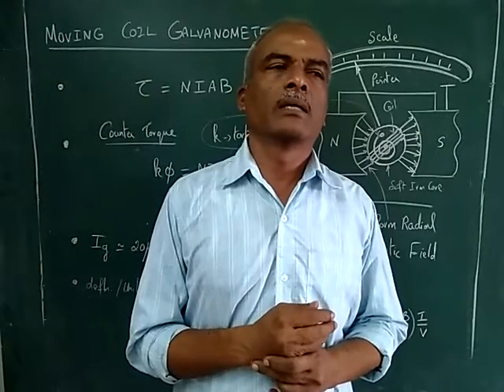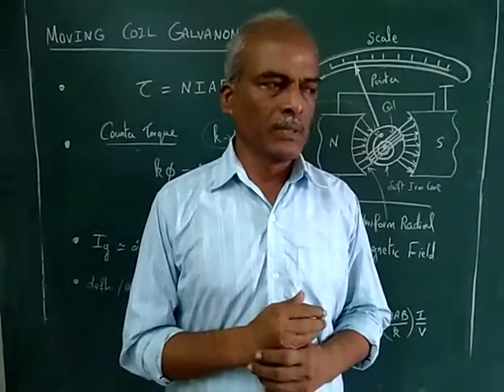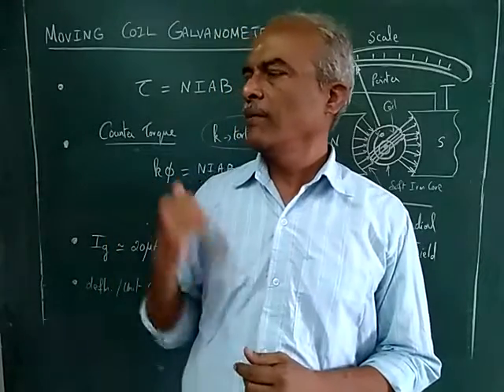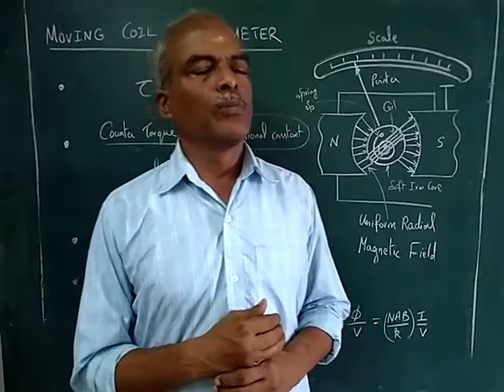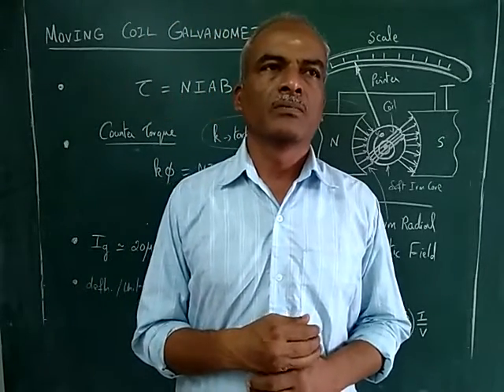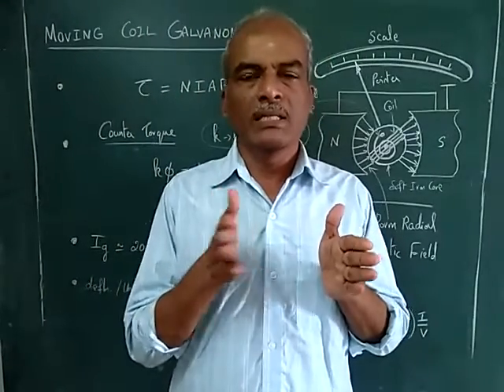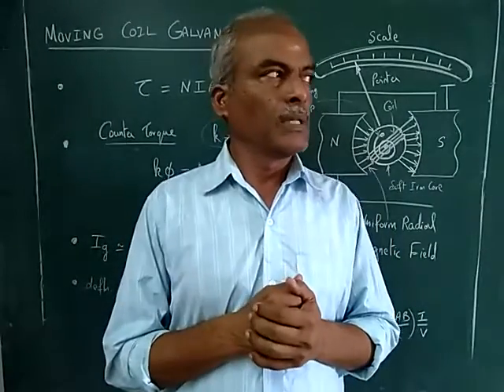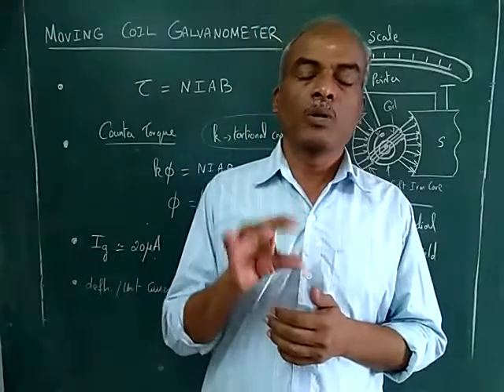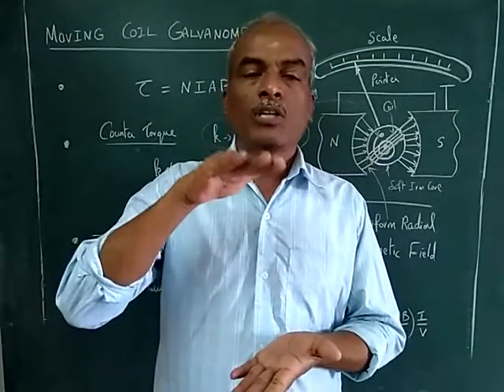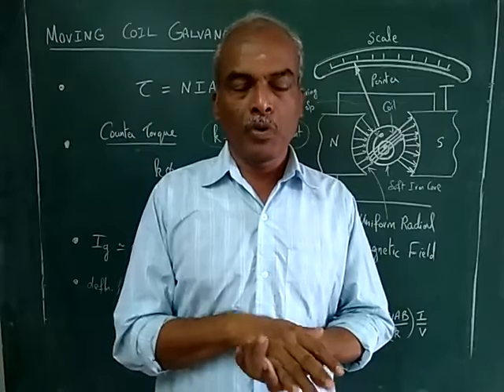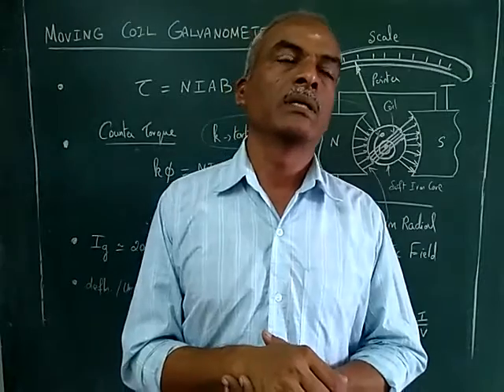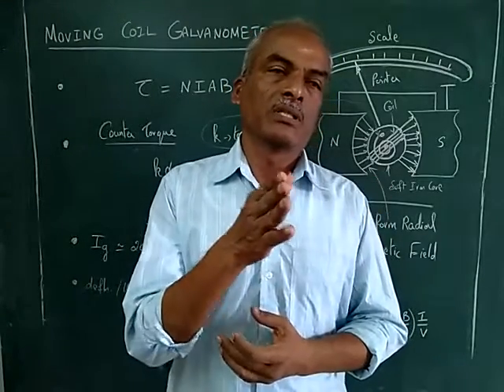In moving coil, the coil will move, whereas in moving iron, the soft iron core will move — that's the difference. In the moving coil meter, there will be a permanent magnet so a magnetic field is established, and in between that steady magnetic field you have a coil suspended. Over the top of the coil you have a pointer with some mechanical balancing arrangement so that it produces deflection.